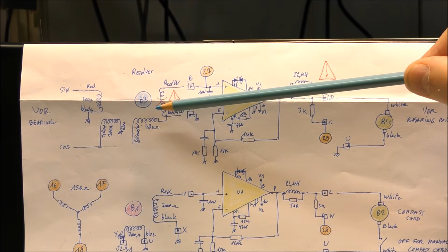There will be an offset of 90 degrees, but it is possible to compensate this offset by changing the position of this resolver. Also, there is a design error concerning this filter, which is not connected for this servo amplifier.